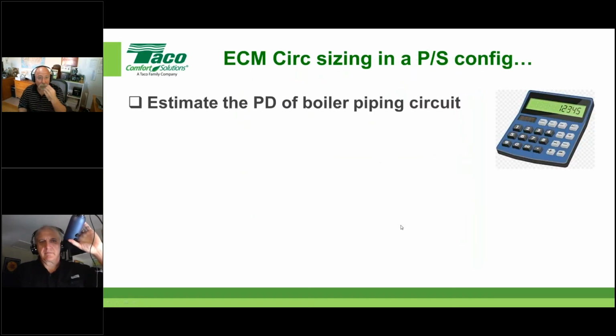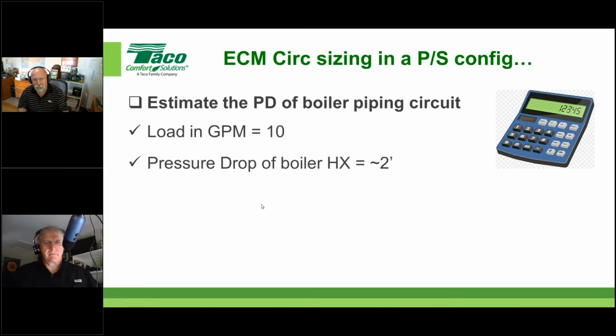Okay. Anyway, the pressure drop estimate. Figure out what the pressure drop of the heat exchanger is. You're going to need some kind of manual, but if you know it's a fire tube style heat exchanger, those are relatively low. Okay, again, I'm showing you at 10 GPM, approximately 2 foot of head.